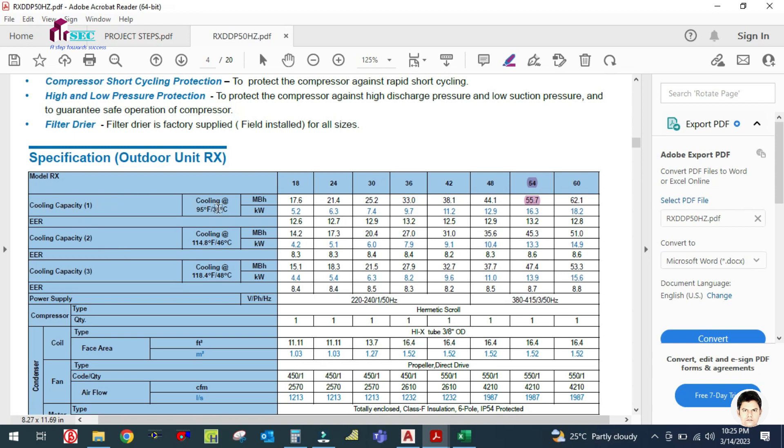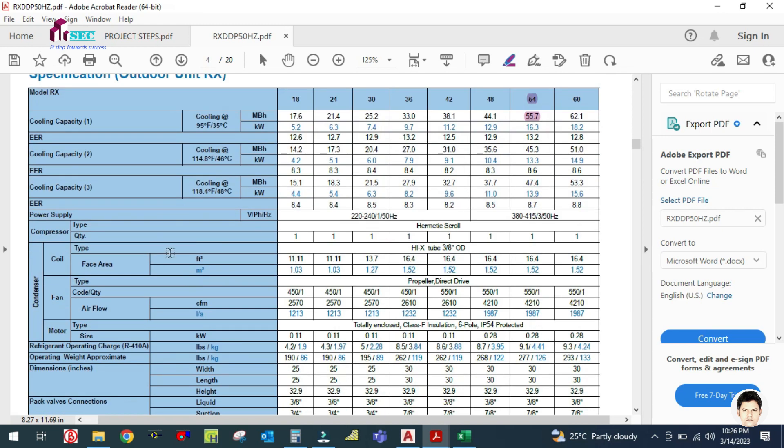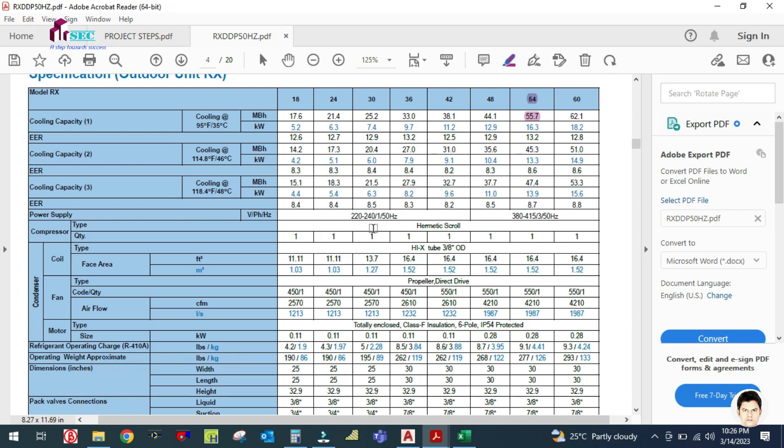Let us see the other parameters here. This is the cooling capacity. This machine is selected at ambient temperature of 35 degrees Celsius T1. T2 is 46 degrees Celsius. Energy efficiency is 8.6, and the power supply is 220-240 volt, single phase, 50 hertz.